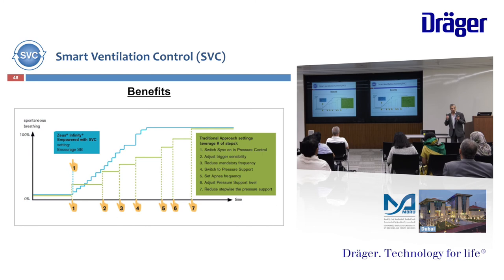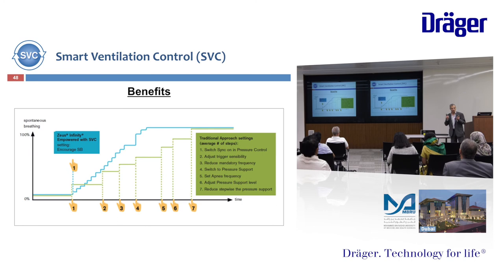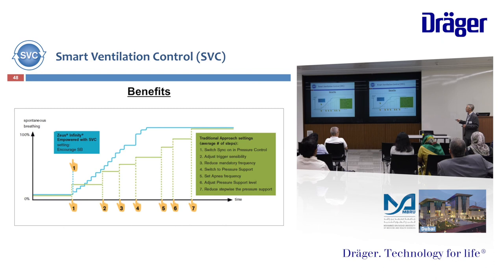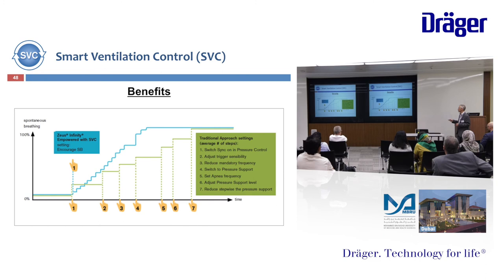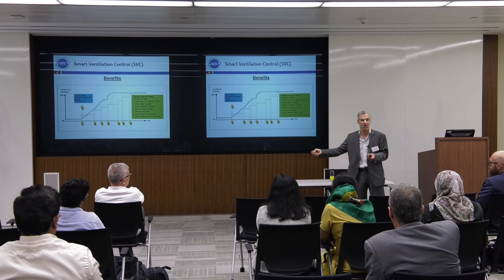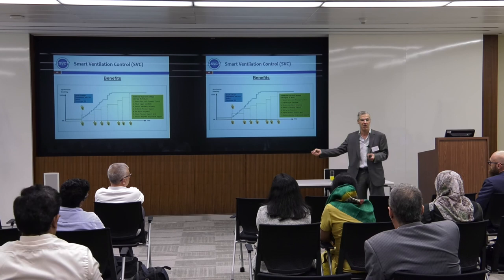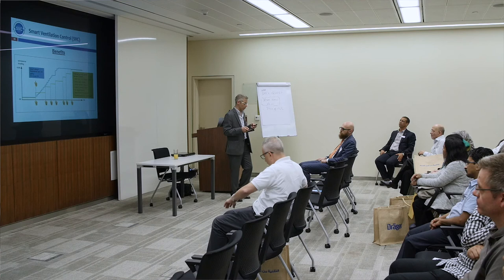And this is the benefit. Just imagine: if I have a patient who is 100% controlled and I would like to return them to 100% spontaneous breathing, what we do now is almost seven to eight steps — switch to synchronized pressure control, adjust trigger sensitivity, reduce mandatory frequency, switch to pressure support, set apnea frequency, adjust pressure support level, then reduce pressure support step by step. I'm doing this if I would like to return the patient's spontaneous breathing while on the ventilator. With the Zeus machine and smart ventilation control, I can do it just with one step.